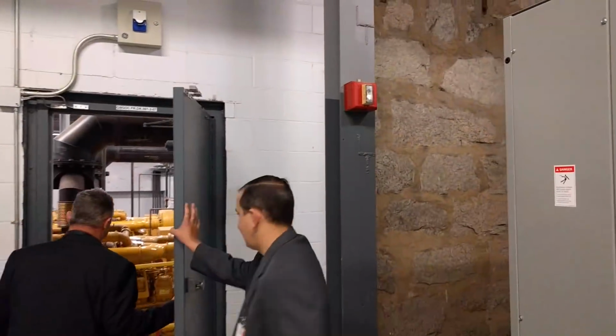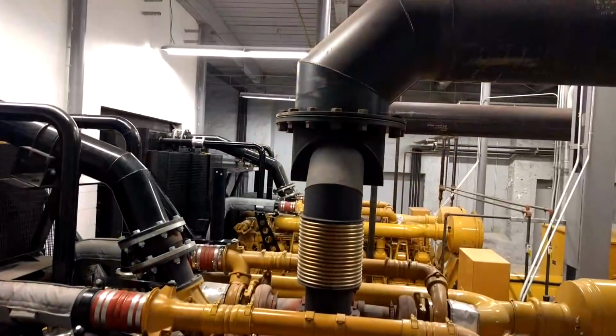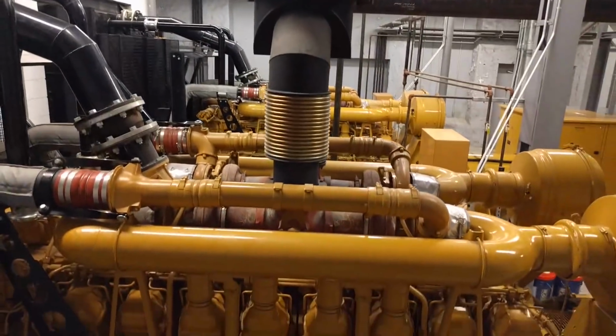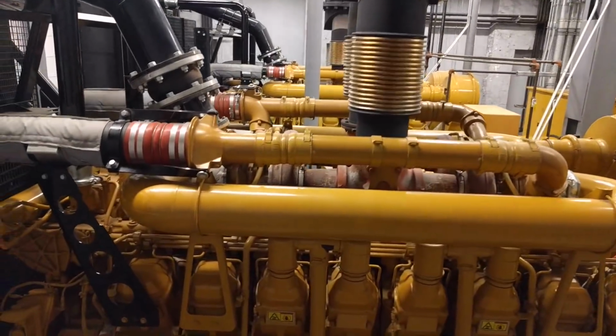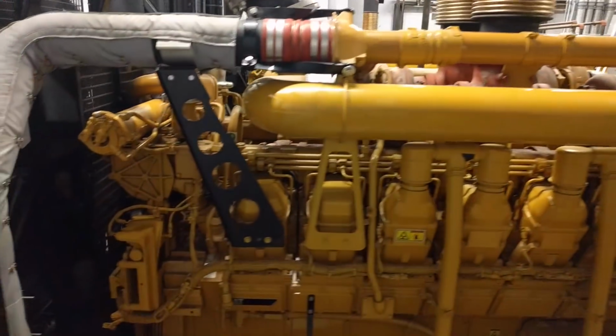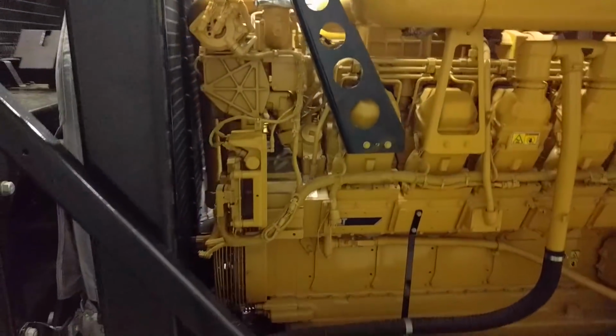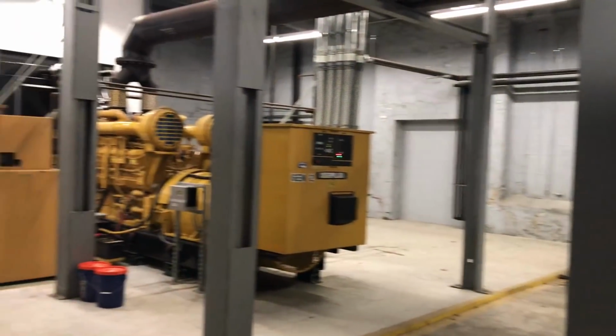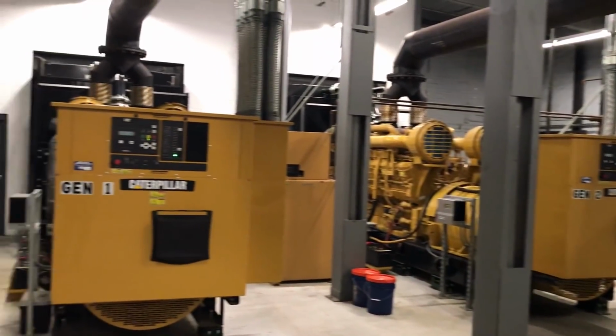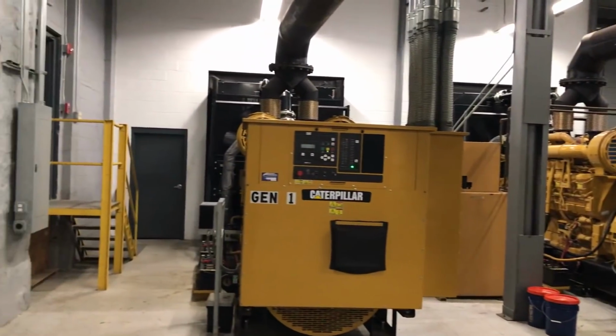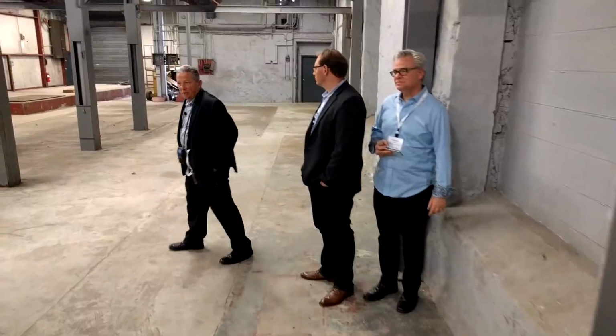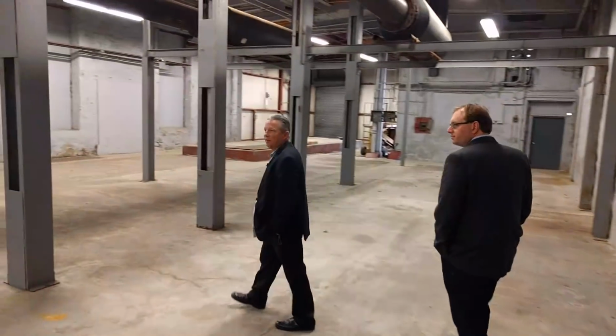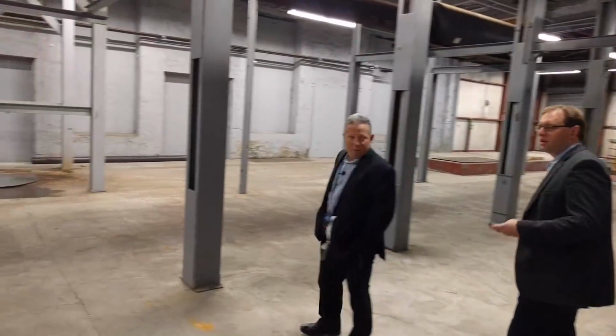You're gonna love this. Little generators right here. Yeah. So these are 2 megawatt each, 16 cylinder, quad turbo, dual starters, 4 batteries, 40,000 pounds, 3,200 horsepower, drink 167 gallons an hour each. 167 gallons of diesel fuel an hour each at full load. Oops, sorry. They each have their own 300-gallon day tank. They each have their own supply and return pumps.